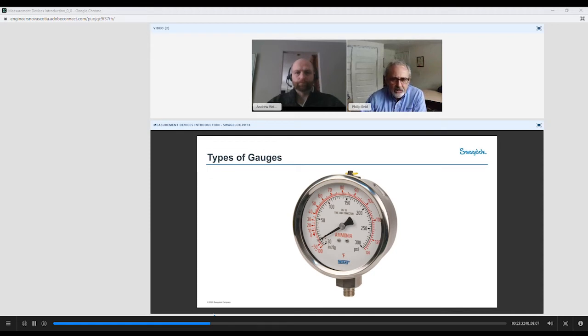Another very common gauge, again very specific to industries, is a pressure-temperature gauge. And people say to me, well, Phil, look at this gauge. It's combining temperature and pressure. So like steam, steam at a specific PSI has a correlating temperature. So if we're looking at 250 pound steam, we're looking at somewhere in the neighborhood of 400 degrees Fahrenheit, or so about 400 degrees Fahrenheit.